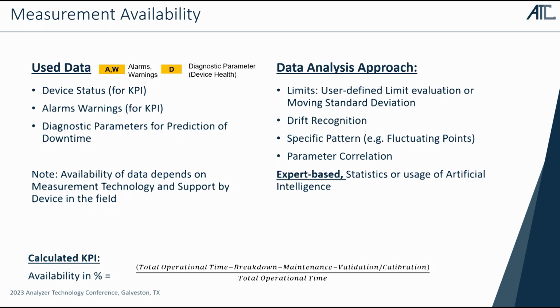To identify drift of this data. So if there's any kind of increasing, decreasing curve, or specific pattern, or if the points are fluctuating heavily, it's also an indication that maybe something is changing there. And also, what we see as very important is that you put these parameters in correlation. Just looking into one value will only in some cases bring you value.